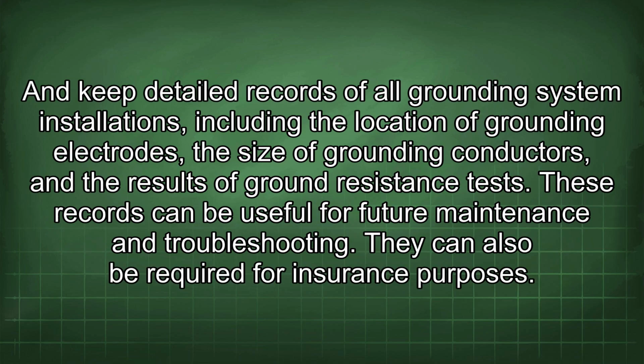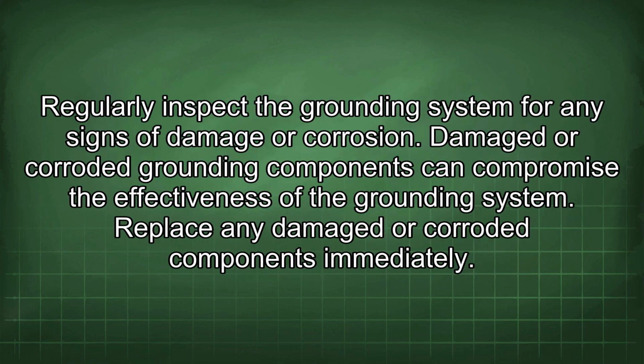And keep detailed records of all grounding system installations, including the location of grounding electrodes, the size of grounding conductors, and the results of ground resistance tests. These records can be useful for future maintenance and troubleshooting. They can also be required for insurance purposes. Regularly inspect the grounding system for any signs of damage or corrosion. Damaged or corroded grounding components can compromise the effectiveness of the grounding system. Replace any damaged or corroded components immediately.